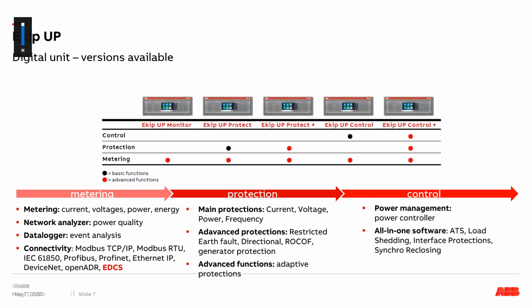Within the metering part, it is able to measure current, voltage, power, and energy. It is also able to provide power quality numbers, and it is able to record events as well, such as data logging activities. It can communicate across multiple protocols: TCP/IP, RTU, which is the old school type of protocol, Profibus, Profinet, Ethernet, and DeviceNet are some of the other ones. IEC 61850 is another protocol the unit can communicate across, and it's one of the most used protocols, especially when talking with medium voltage relays. And of course, it can communicate across our own electrical distribution control system, the EDCS platform.